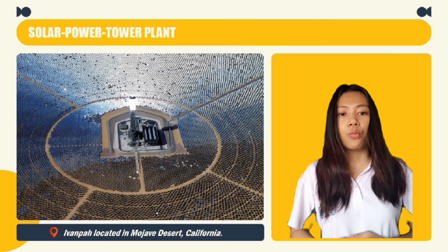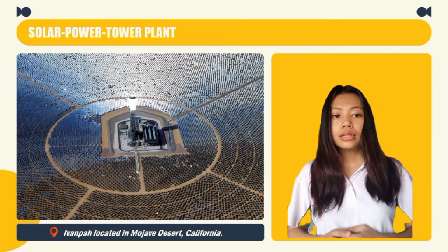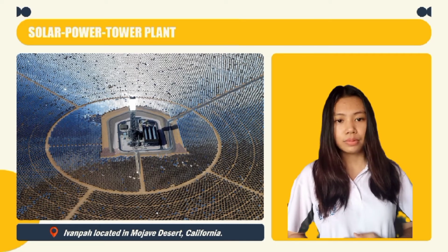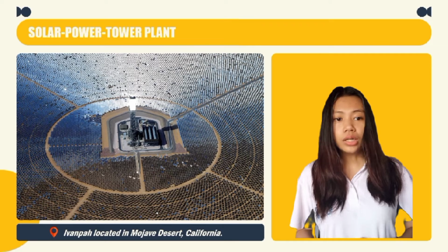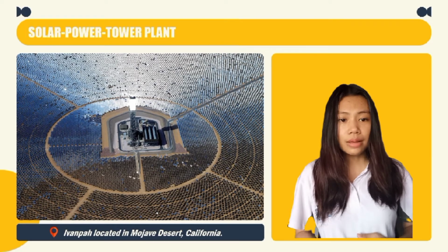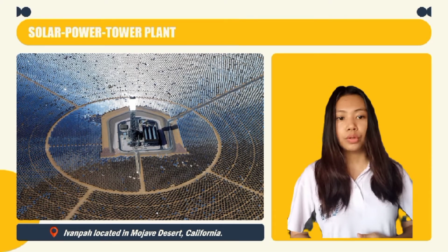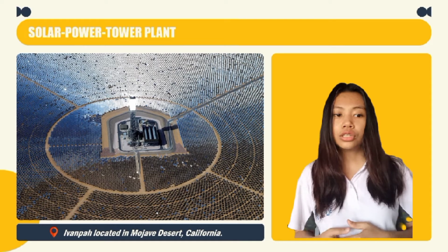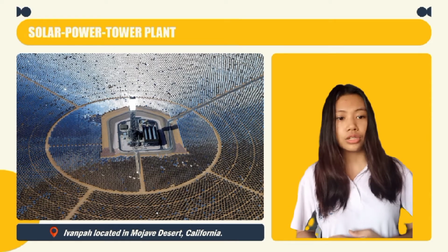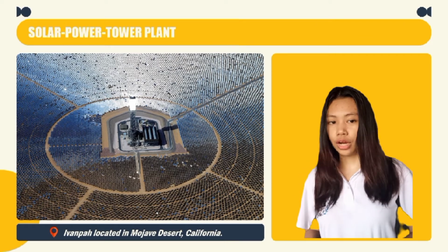The towers are 140 meters high. The solar energy is absorbed by water flowing in the pipes of the boiler. The water turns into superheated vapor, which is directed into a steam turbine located at the bottom of the tower. Electrical output from the turbine is sent to transmission lines. This plant uses an air-cooled condenser, which uses 95% less water than a wet-cooled solar thermal plant.